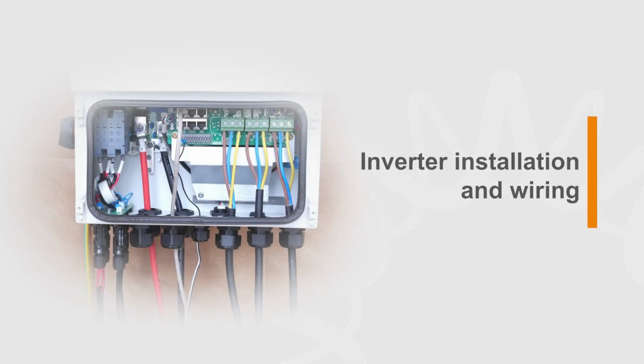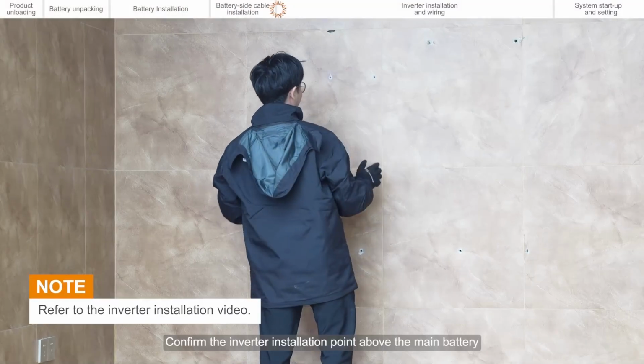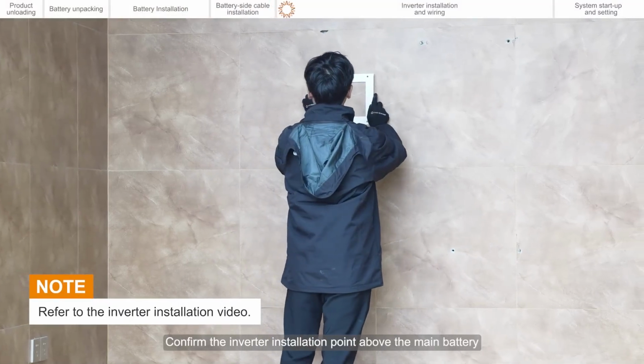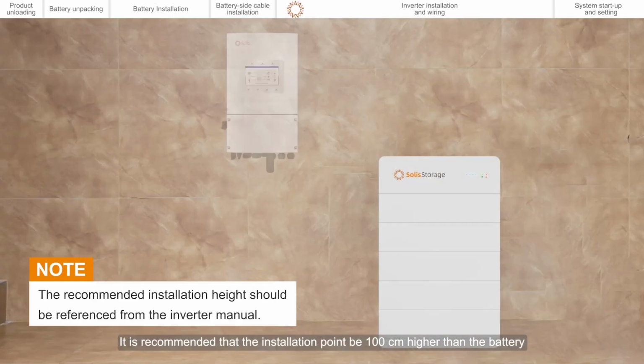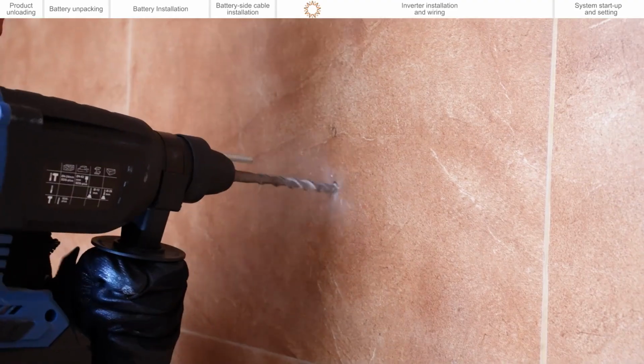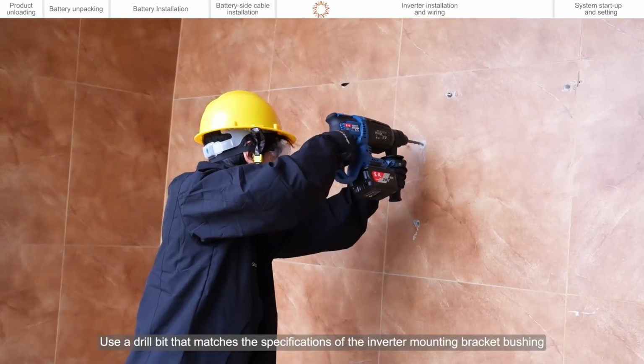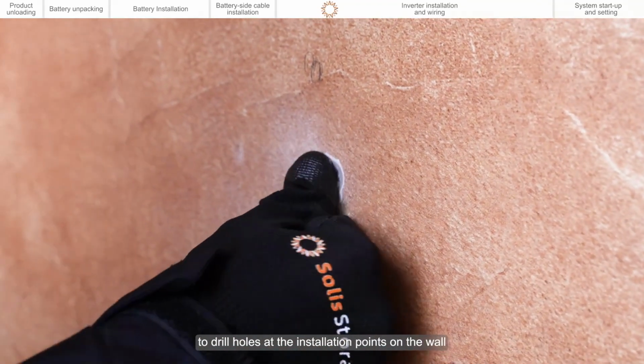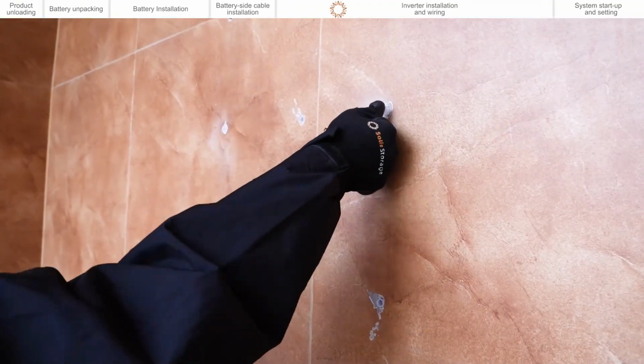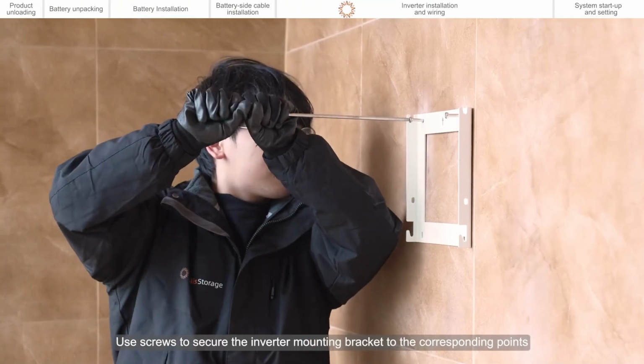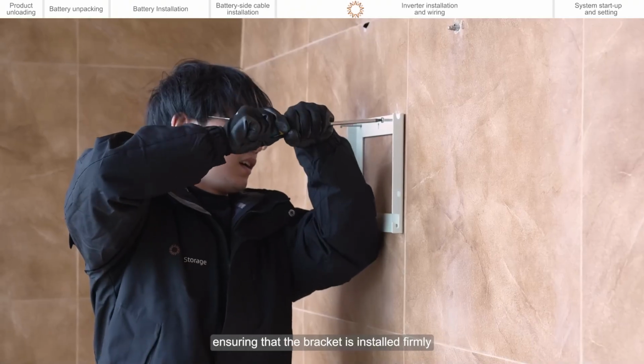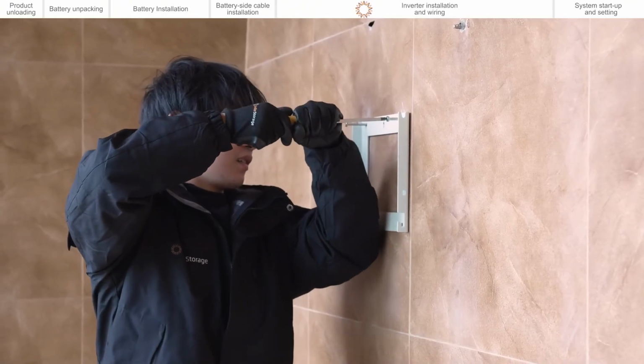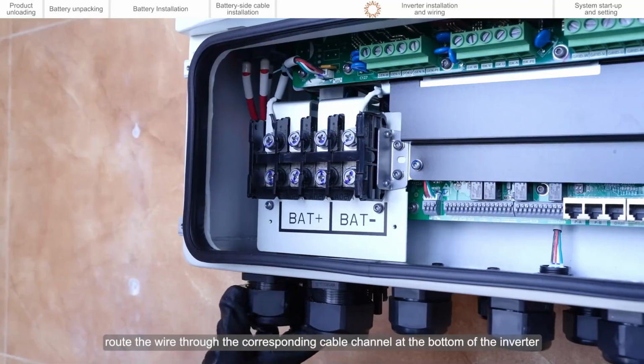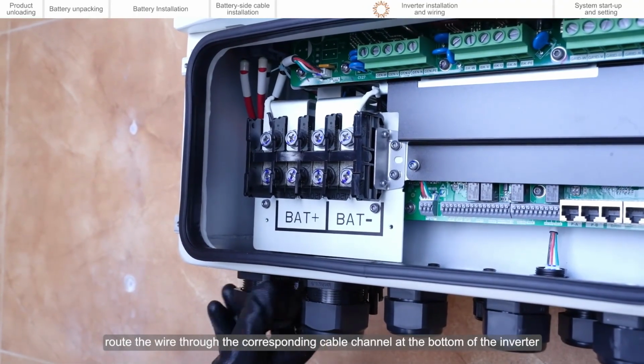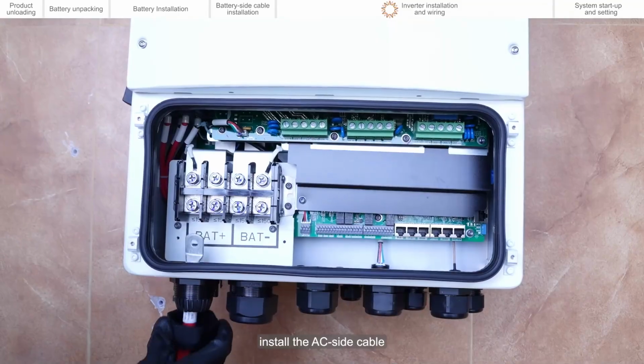Inverter installation and wiring. Confirm the inverter installation point above the main battery. It is recommended that the installation point be 100 centimeters higher than the battery. Use a drill bit that matches the specifications of the inverter mounting bracket bushing to drill holes at the installation points on the wall. Use screws to secure the inverter mounting bracket to the corresponding points, ensuring that the bracket is installed firmly. According to the cable type, route the wire through the corresponding cable channel at the bottom of the inverter. Install the AC side cable.